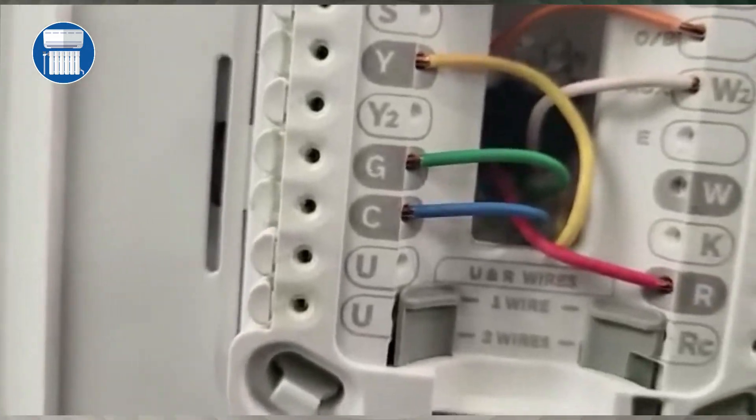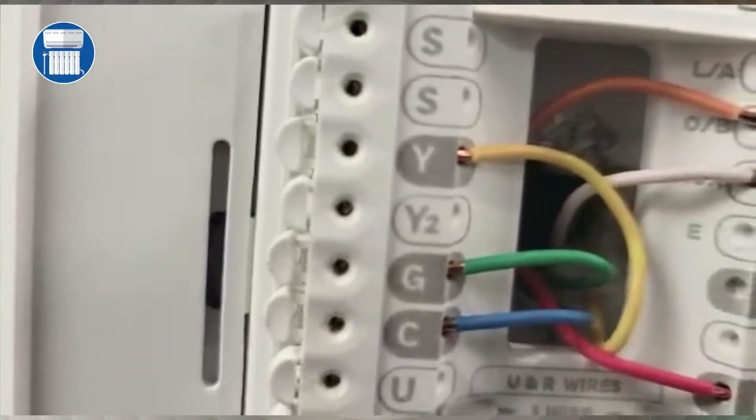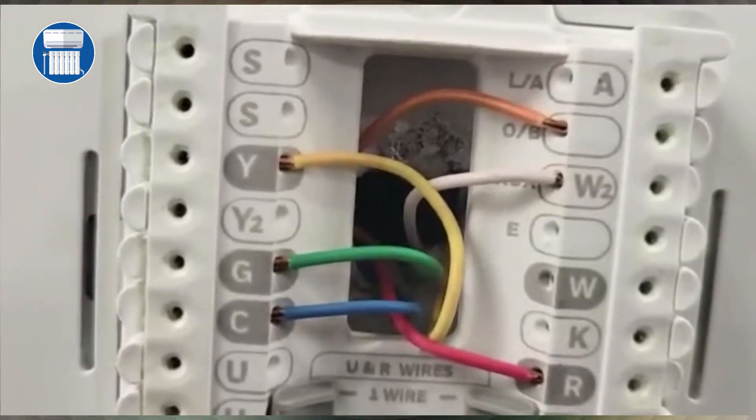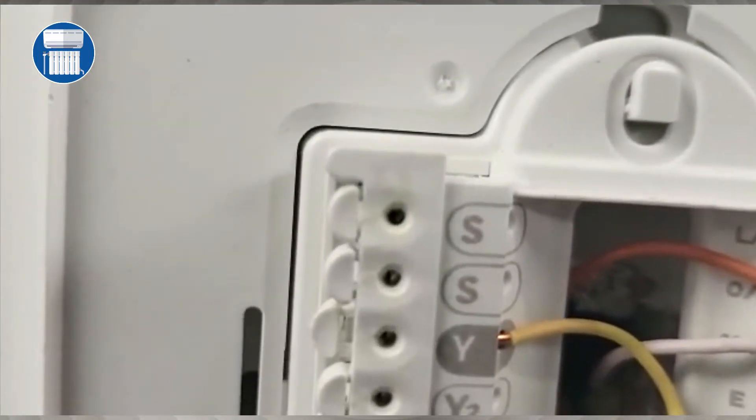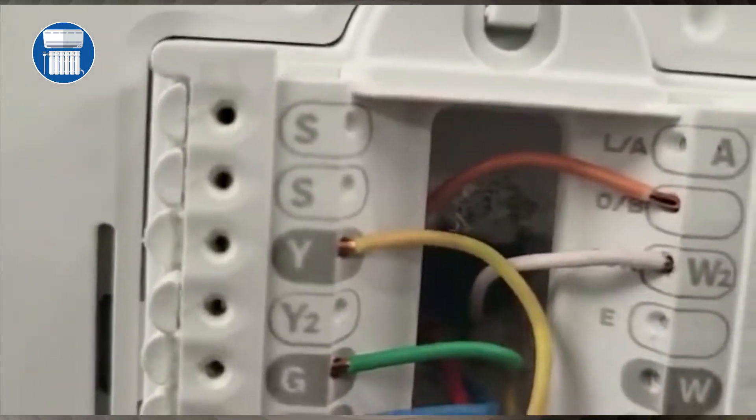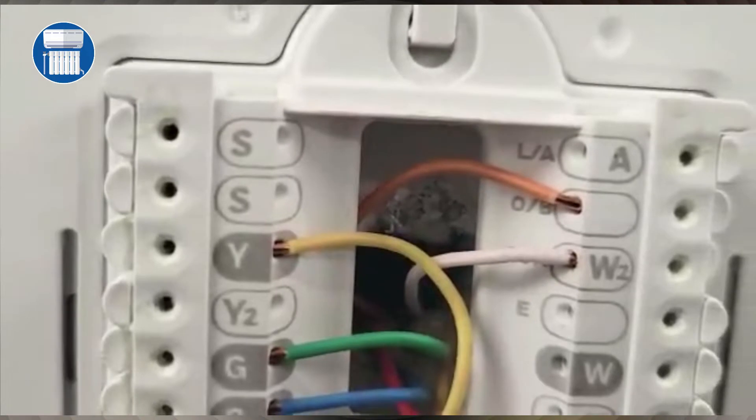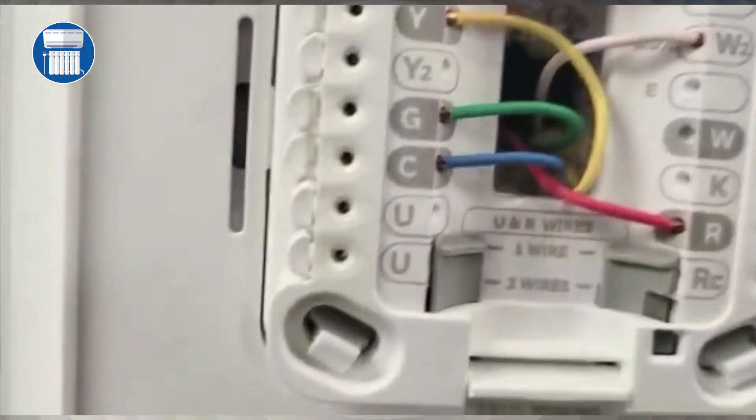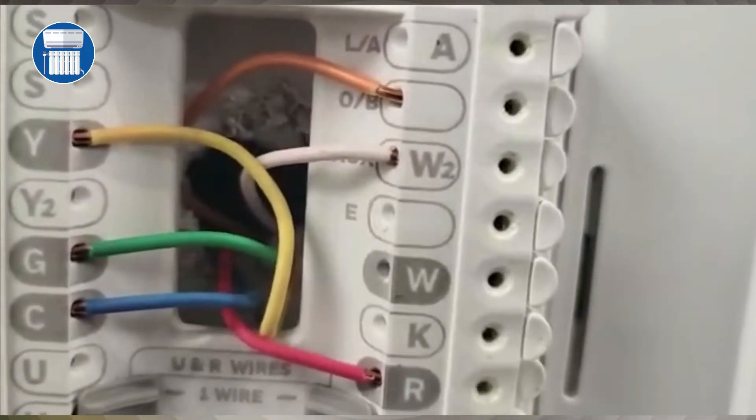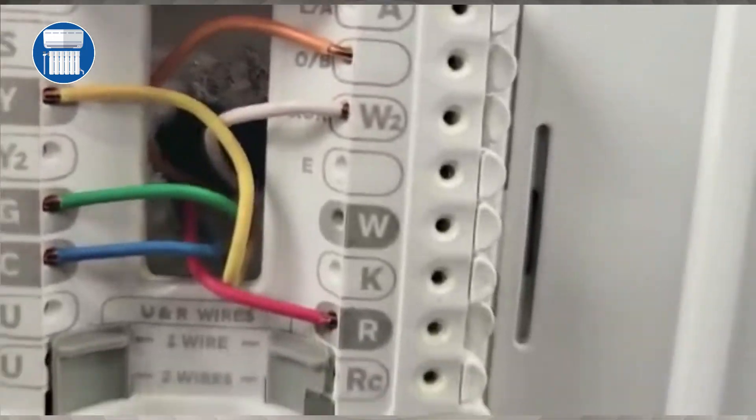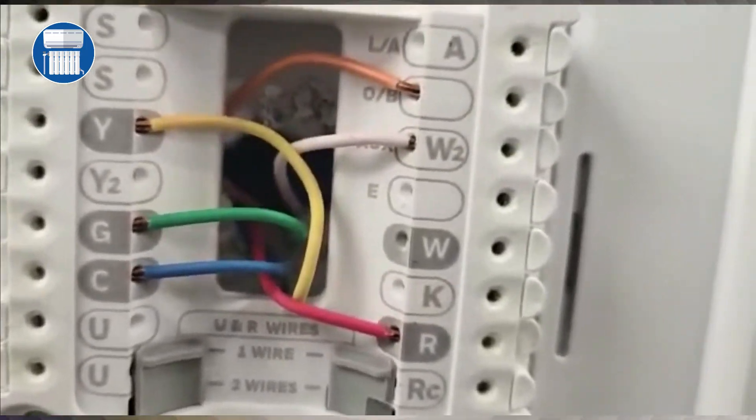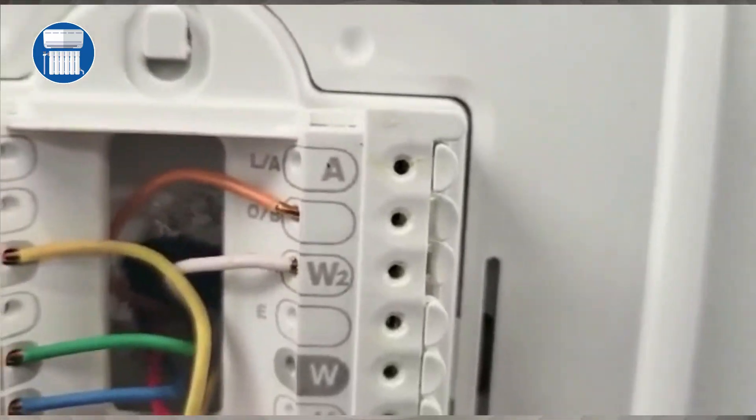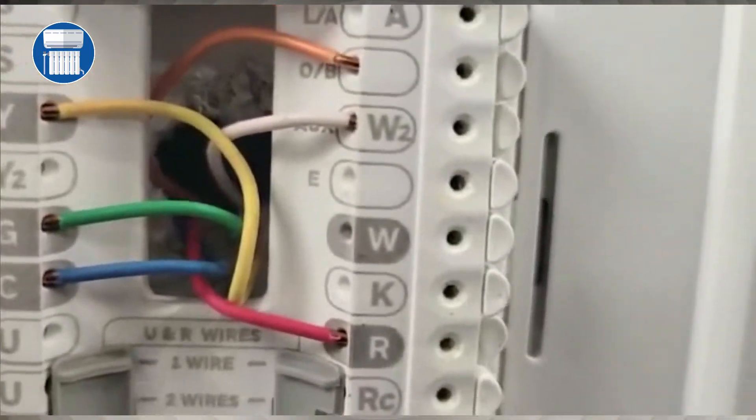Next, do your green wire. That is your fan, so connect that green wire to the green terminal on your thermostat. Then do your yellow or Y terminal. That is for your cooling. In this instance it has a two-stage, so we have it on W2. But if you have a one-stage system, you could put your white wire for your heat on W.